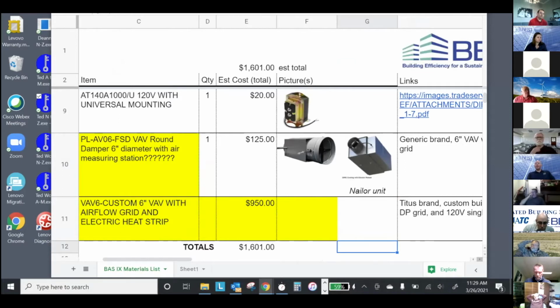One of the great things about the VAV box is that, until you get into a specialty one like a 120 volt electrical reheat, which is where we went with this, they're pretty cheap. That $125 quote is for just a plain 6-inch VAV box with an airflow measuring grid and damper — really the bare minimum you can get away with for this project. But VAVs with hot water reheat coils are very common and usually pretty affordable, so we've got multiple price points depending on what you're capable of providing or what you already have.